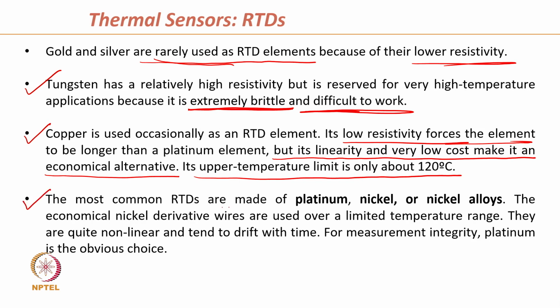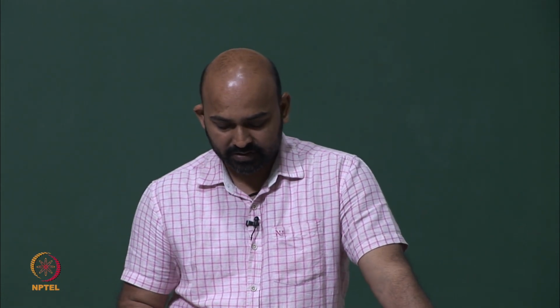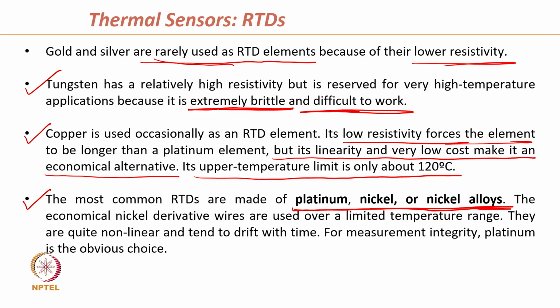The most common RTDs are made up of platinum, nickel or nickel alloys. These are the materials which are commonly used for RTD fabrication. Though these metals are costly, because we are using very thin film of these materials, the cost of the material comes down and we can still use these expensive metals. The economical nickel derivative wires are used over a limited temperature range. They are quite non-linear and tend to drift with time. For measurement integrity, platinum is the obvious choice.